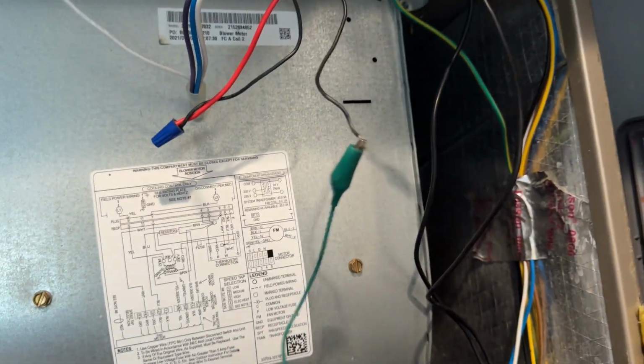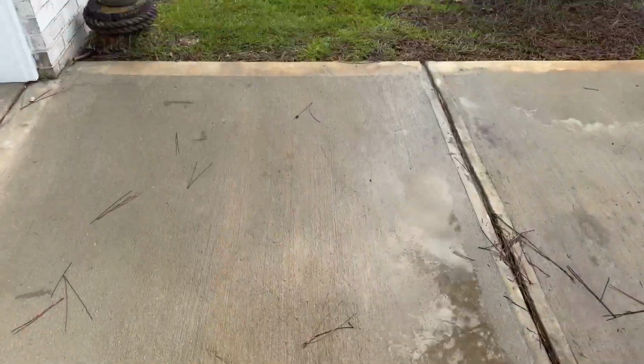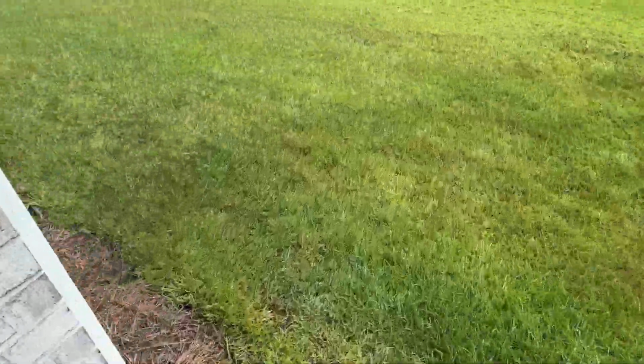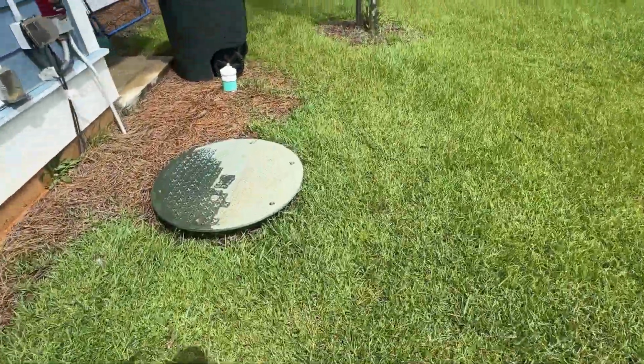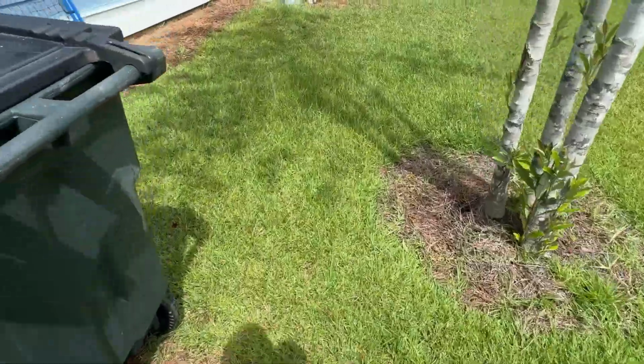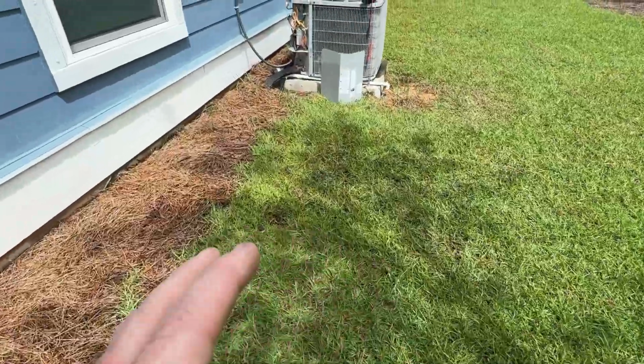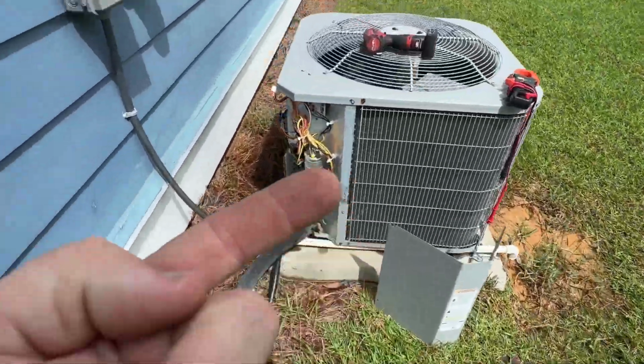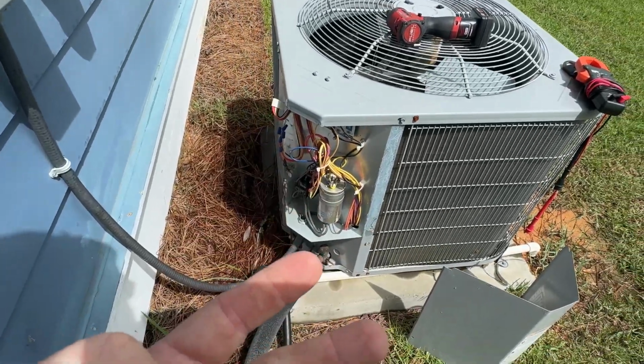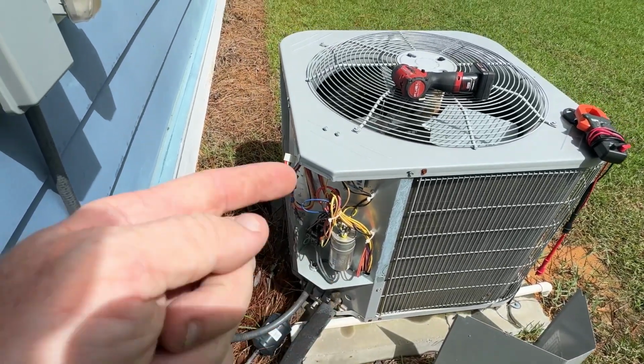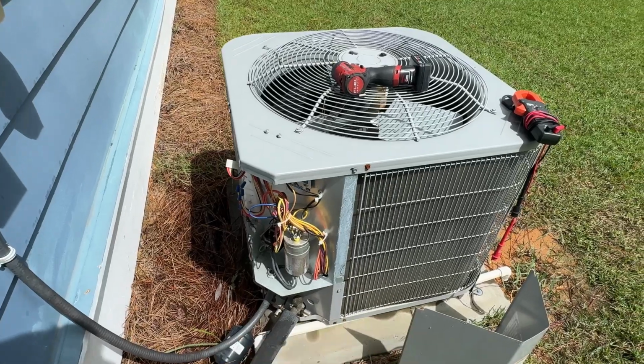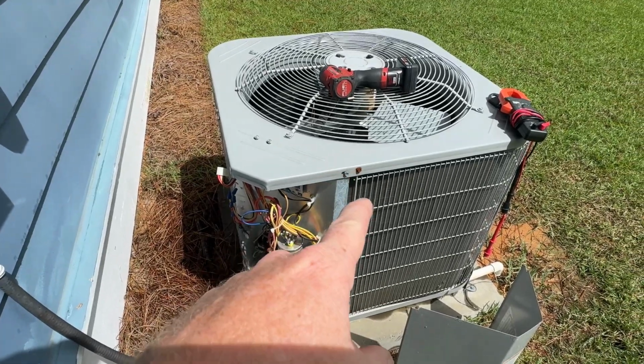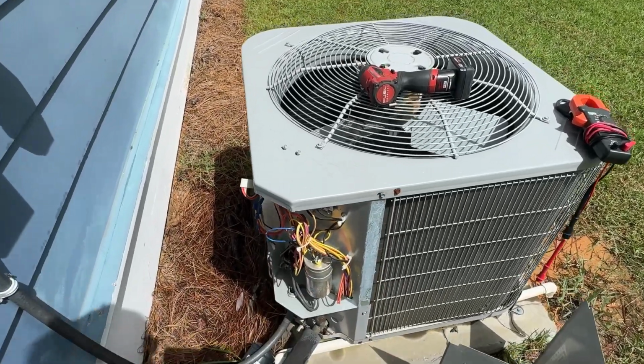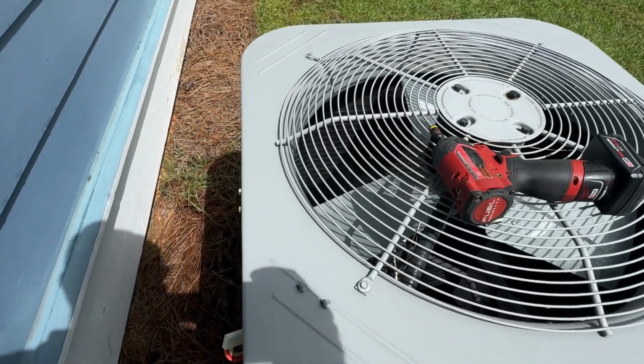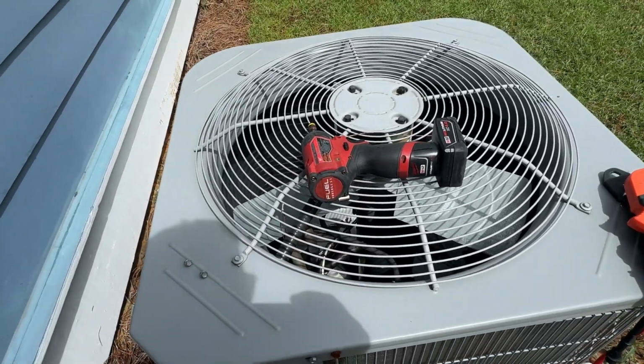All right, I'm back outside. So after you unplug that board, there's nothing in the wiring. Nothing shorting out, so wiring going inside is fine. So now we need to focus on the components out here. We focus on the board and the reversing valve solenoid. So you can either plug stuff in and keep unplugging stuff to get to it. I'm gonna start with the reversing valve solenoid and work backwards now. That's what I like to do once I figure out the area that the main issue's in.